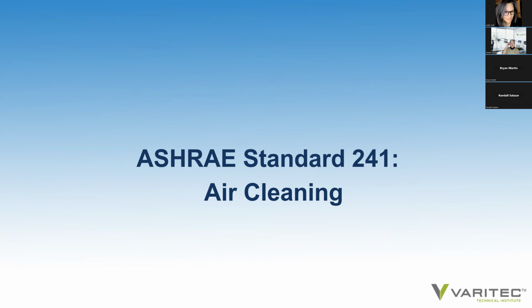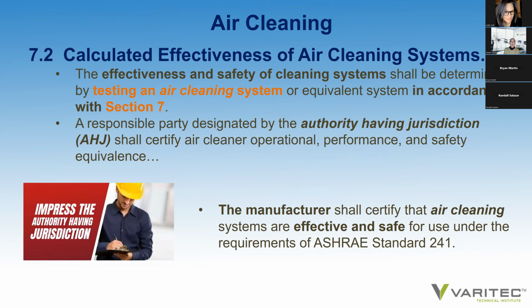So let's look at ASHRAE Standard 241 and air cleaning. What is air cleaning? This is a little complicated, so bear with me here. I'll try to navigate and find the language to make it accessible. In the air cleaning section of the standard, section 7.2 offers a calculated effectiveness of air cleaning systems. That is to say, how effective is a technology in removing infectious aerosols? What percentage of clean air can come free of aerosols, or of inactivating or actually containing infectious aerosols?